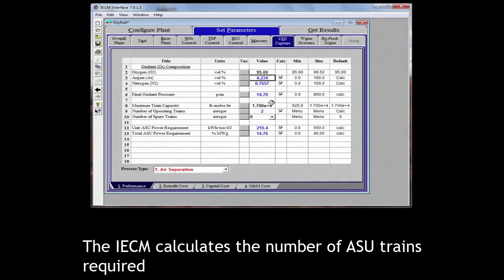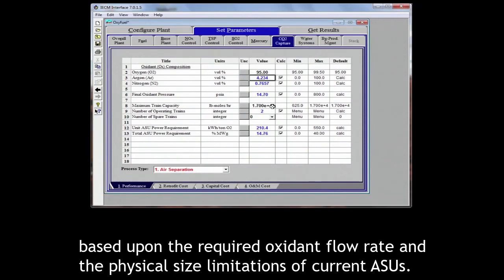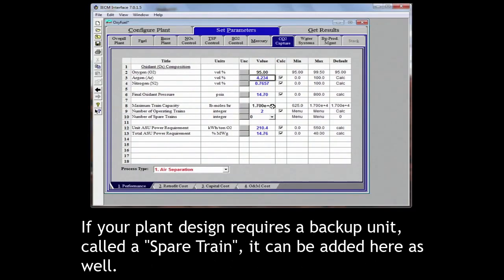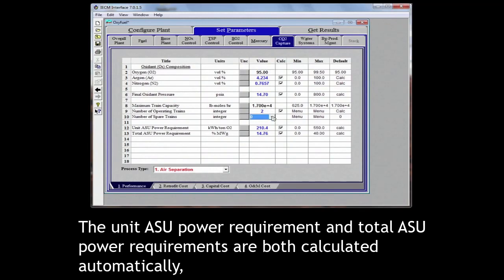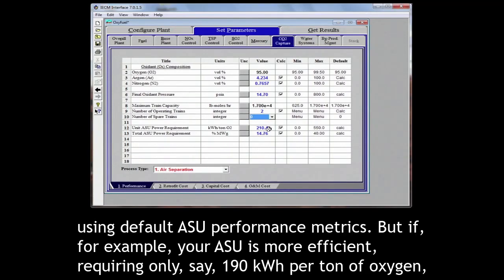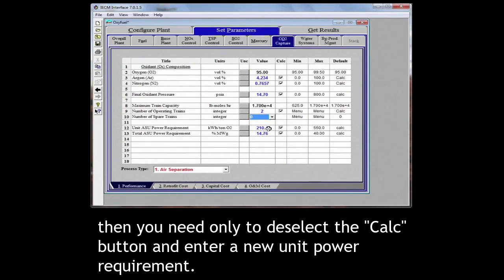The IECM calculates the number of ASU trains required based upon the required oxidant flow rate and the physical size limitations of current ASUs. If your plant design requires a backup unit, called a spare train, it can be added here as well. The unit ASU power requirement and total ASU power requirements are both calculated automatically using default ASU performance metrics. But if, for example, your ASU is more efficient, requiring only say 190 kWh per ton of oxygen, then you need only to deselect the calc button and enter a new unit power requirement.